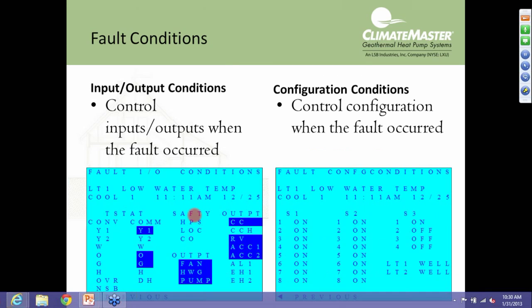And then any of our input-output conditions. So over here you can see if you're getting an input from a communicating thermostat, Y1, O and G, and then any safeties if we had a high pressure switch open, our outputs, our fan, our hot water generator, our loop pump. Outputs over here, CC is our compressor contactor, CCH would be our power going up to that rectifier for the Ultratech scroll compressor. RV is the reversing valve. And then our dip switch positions at the time of the fault.